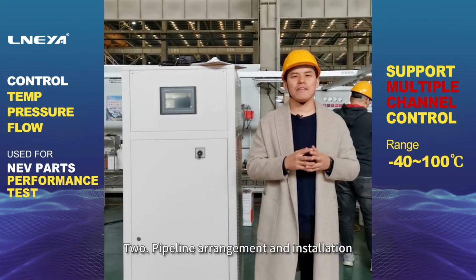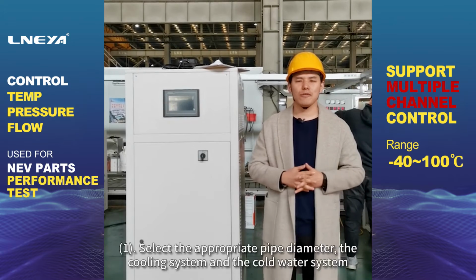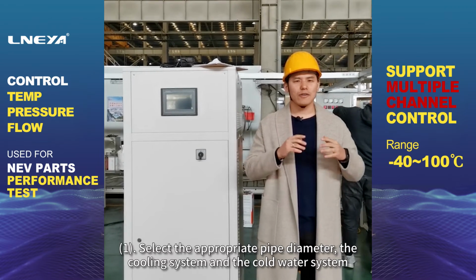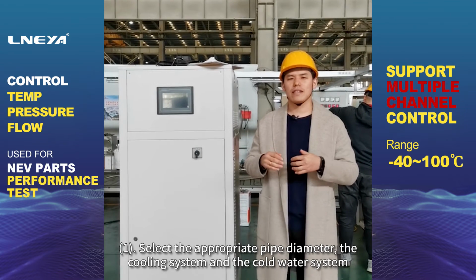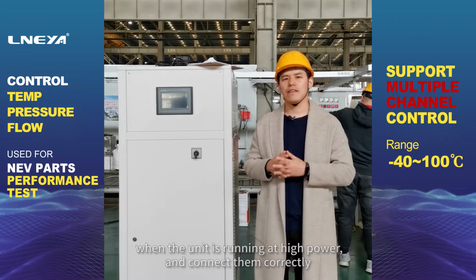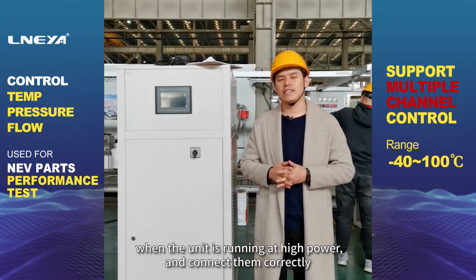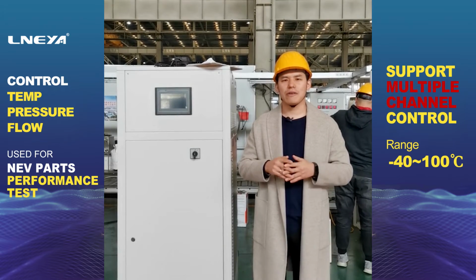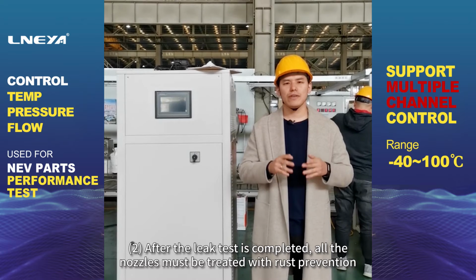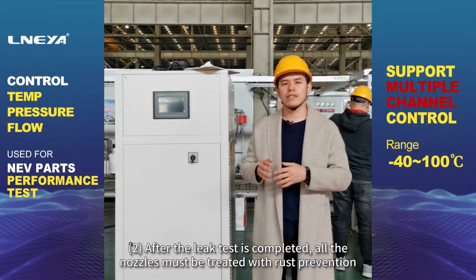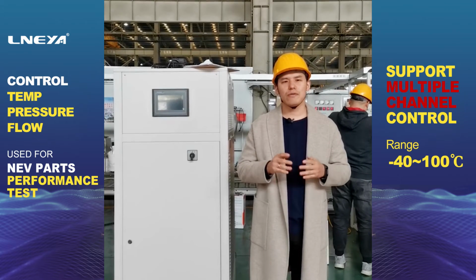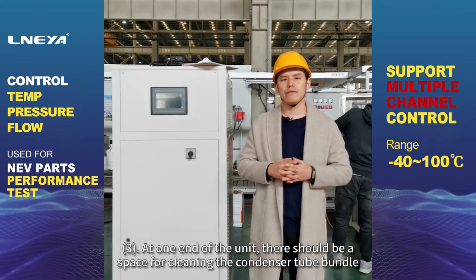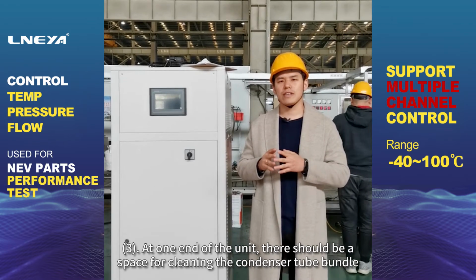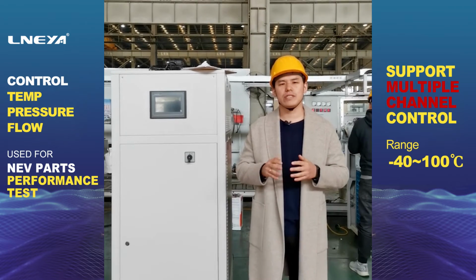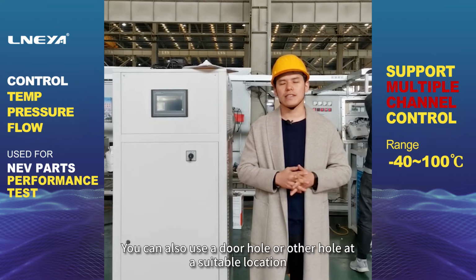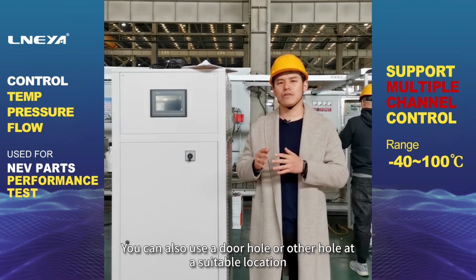Second, pipeline arrangement and installation. 1. Select the appropriate pipe diameter, the cooling system and the cold water system when the unit is running at high power, and connect them correctly. 2. After the leak test is completed, all the nozzles must be treated with rust prevention. 3. At one end of the unit, there should be a space for cleaning the condenser tube bundle. You can also use a door hole or other hole at a suitable location.